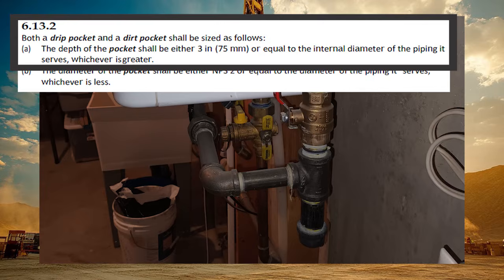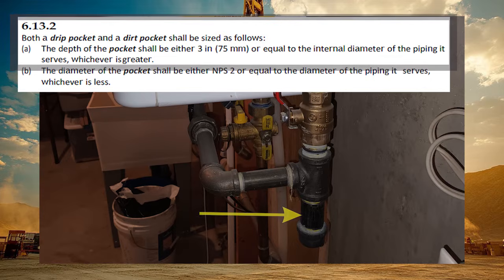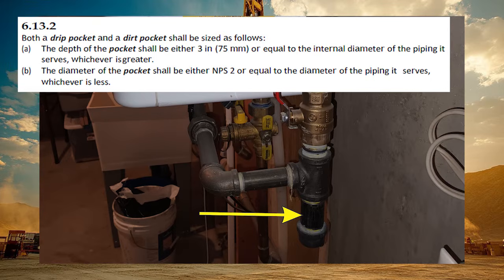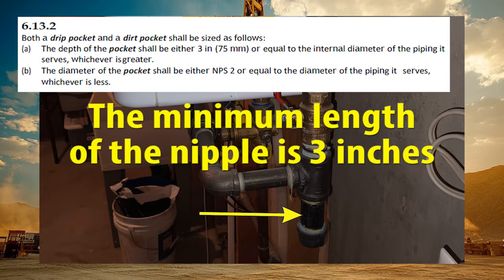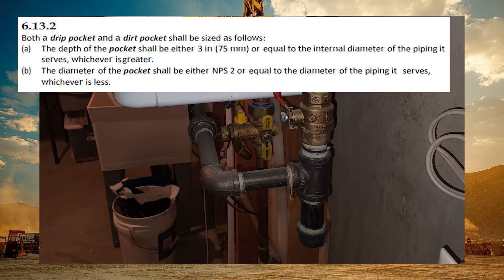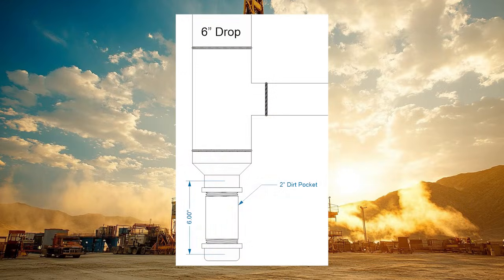Now, instead of referring to the depth of a dirt pocket, what I'm going to say is we're talking about the length of the nipple that's between the T and the cap. The minimum length according to this code is 3 inches long. The part of this clause that confuses some people is where it's referring to the internal diameter of the piping drop. What they're saying is when we have large piping systems, greater than 3 inches in size, we need to match the length of that nipple with the internal diameter.